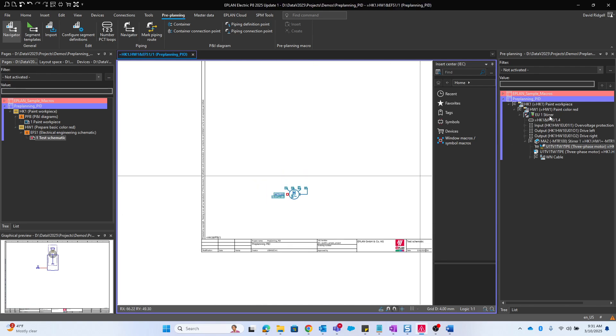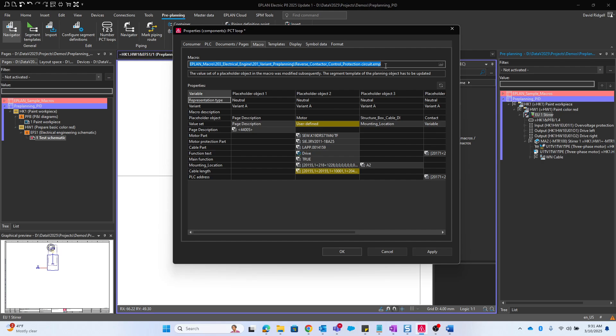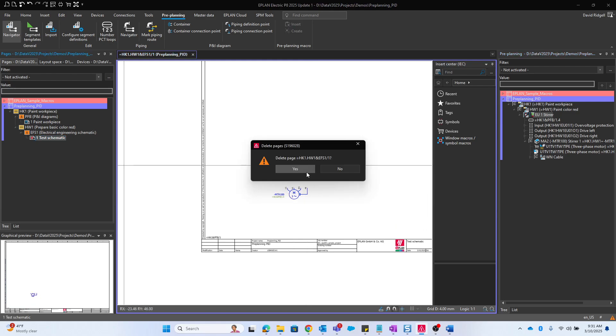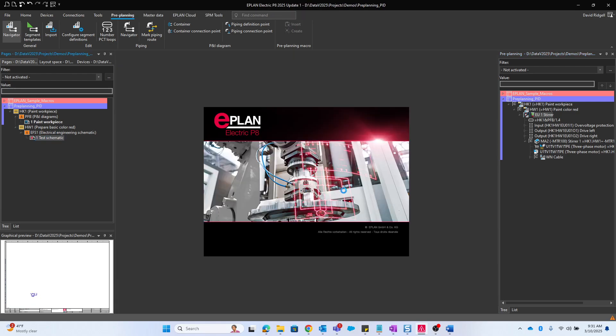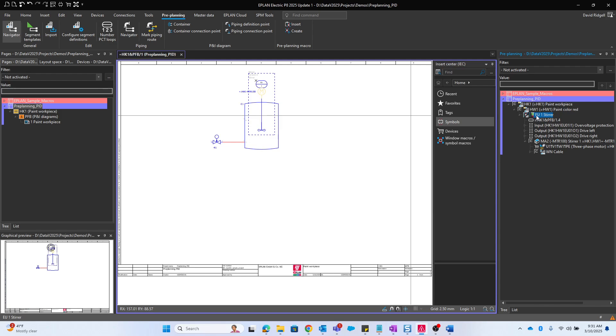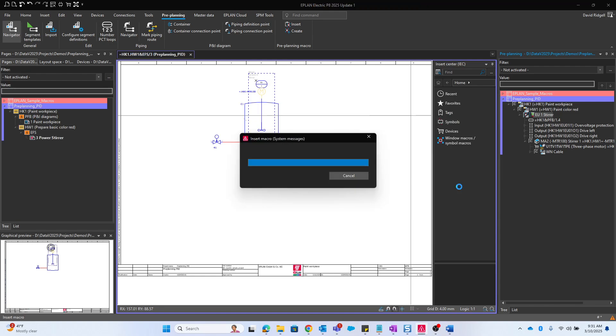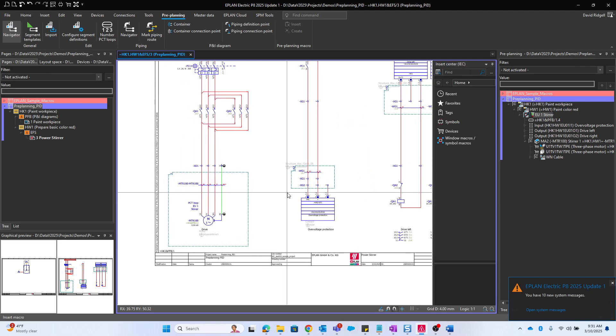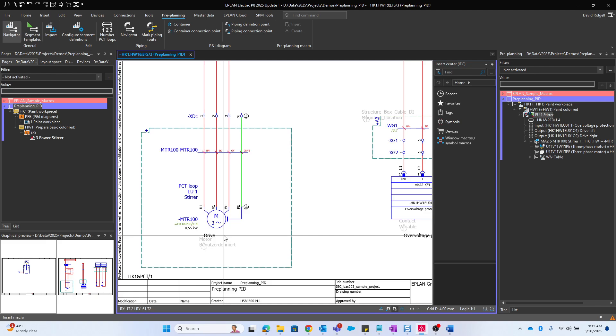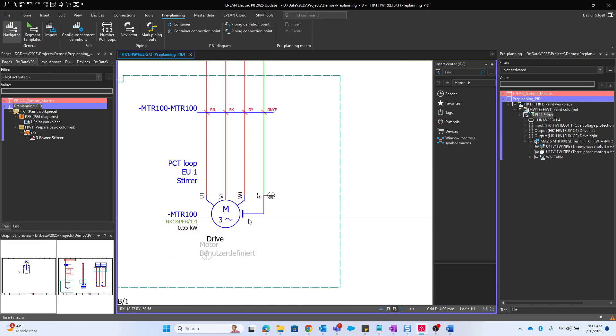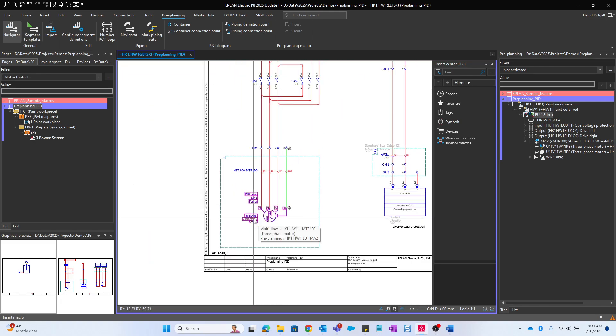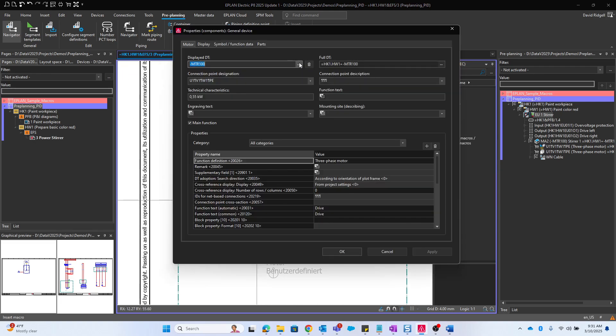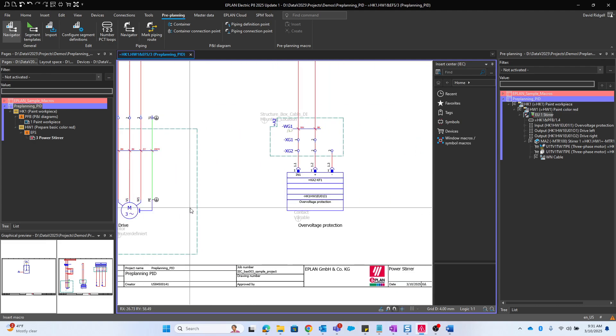But we remember that if we go upstream, we have that macro at the PCT loop level. In this case we can actually automate the schematic. I'm going to go ahead and delete this test schematic. Then just from the preplanning navigator, I'll take this PCT loop with the macro attached to it, drag it over to the page navigator, drop it in. Here we see that it's placed. It picks up that device tag from the product aspect. Then it also displays properties of the PCT loop here at the motor.